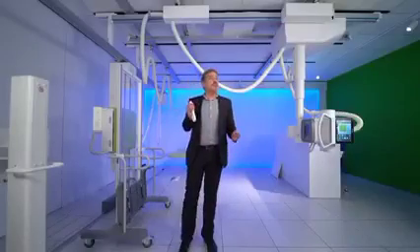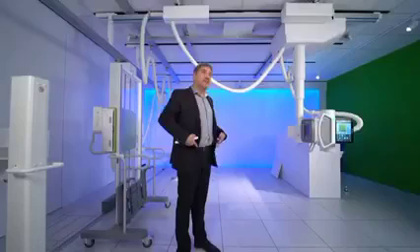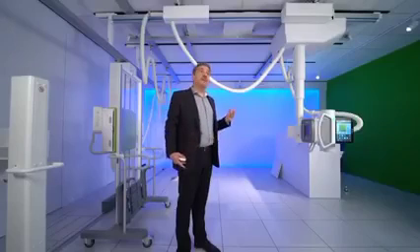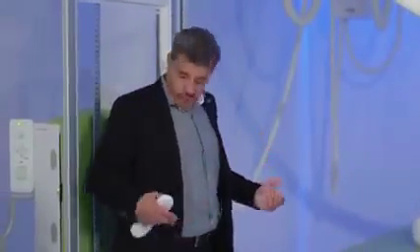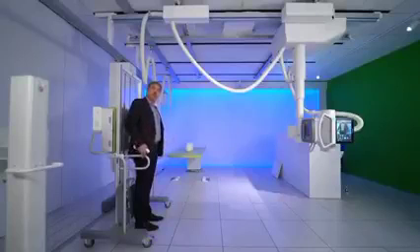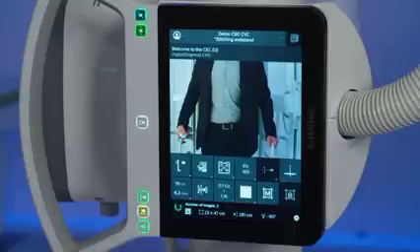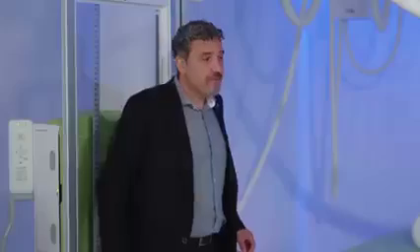Another examination you might need is stitching. Stitching of the full spine or the full legs just by creating 2 or 3 exposures while the system will stitch those images together automatically. How it is done with the C90, it's very simple. The patient is going to stand in front of the wall stand, either on top of this footrest or for spine, they can just stand on the floor. They can comfortably hold on to the system to find more balance and to stand in a stable way.